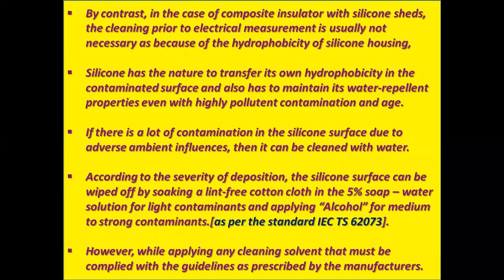If there is a lot of contamination on the silicone surface due to adverse ambient influences, then it can be cleaned with water. According to the severity of deposition, the silicone surface can be wiped off by soaking a lint-free cotton cloth in a 5% soap water solution for light contaminants and applying alcohol for medium to strong contaminants, as per standard IEC 62073.